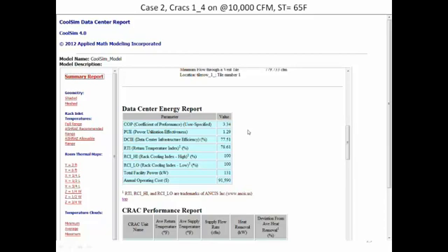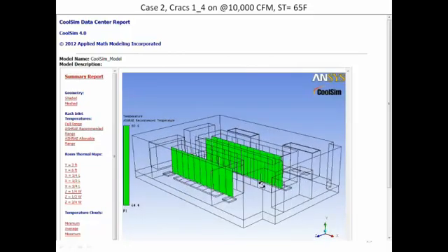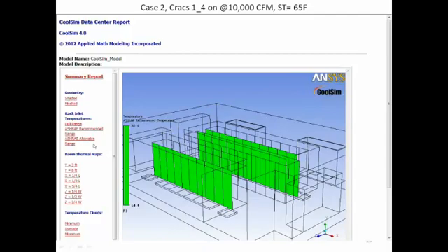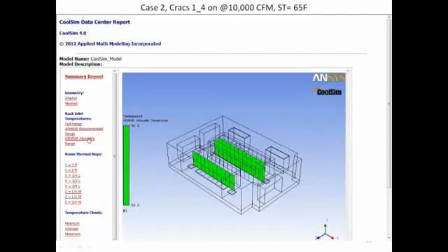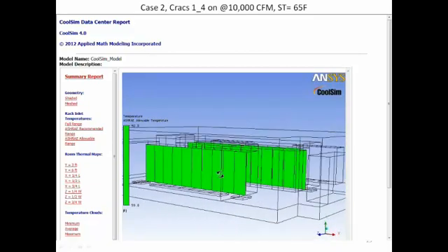Annual operating cost $91,000. So here again, Magnus, I think we've gotten right to that balance point, with RTI not quite 100, but right up there near 80, and the other two at 100. And also, to add something else, Paul, I think there's a point where you have to stop the optimization because it's going to cost you too much in first cost. Right. Yeah, that was my point before.